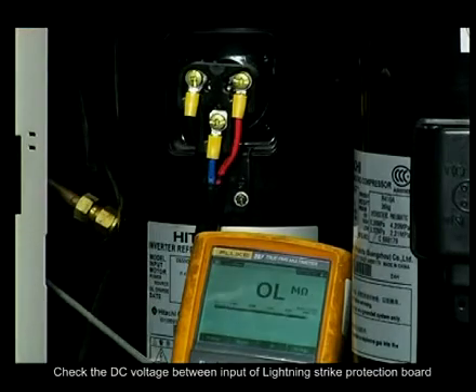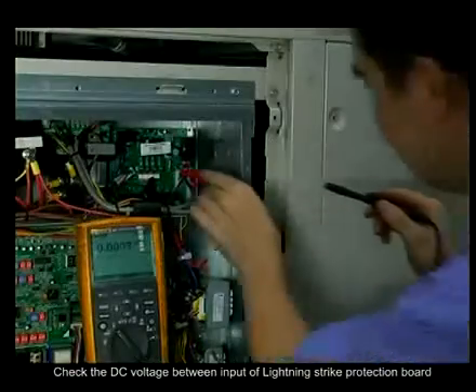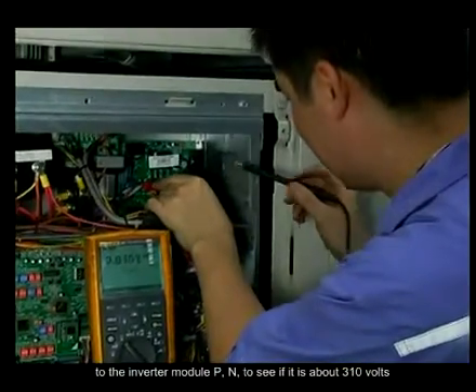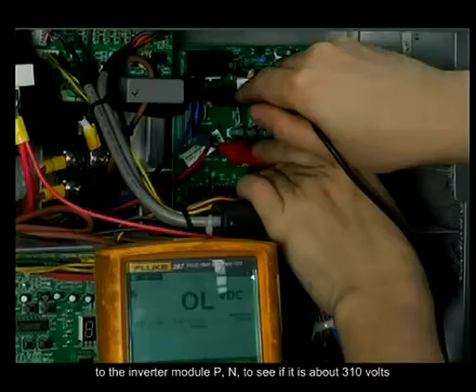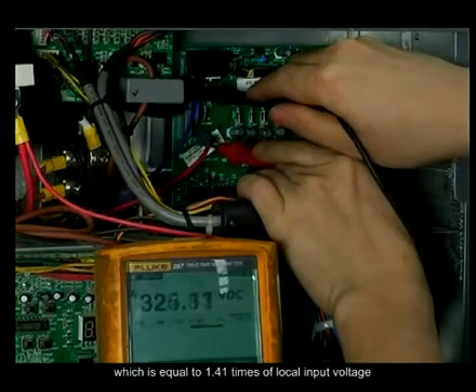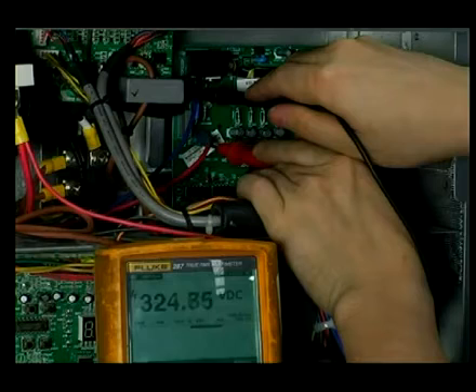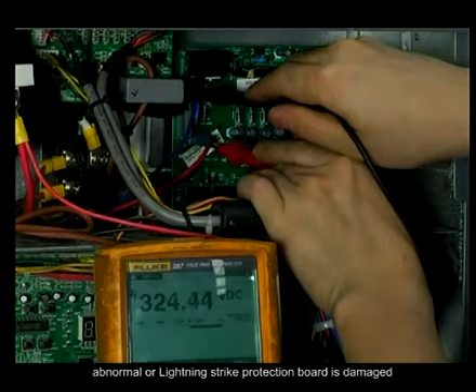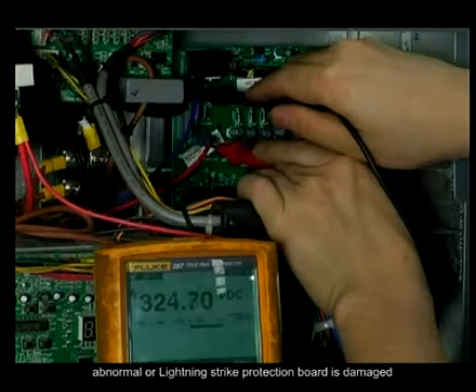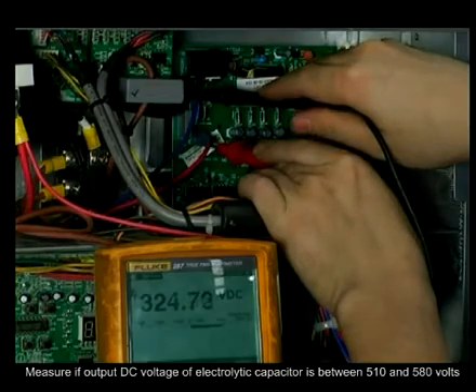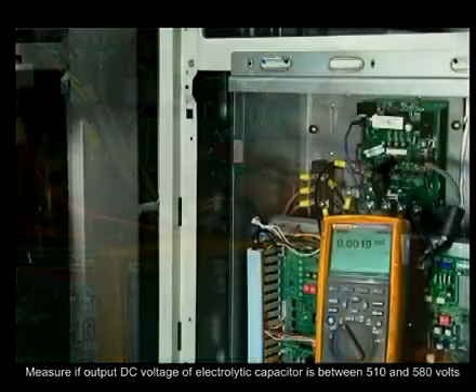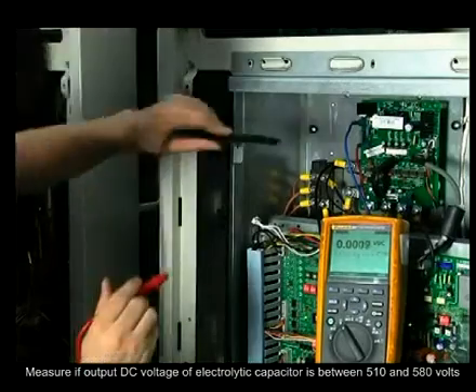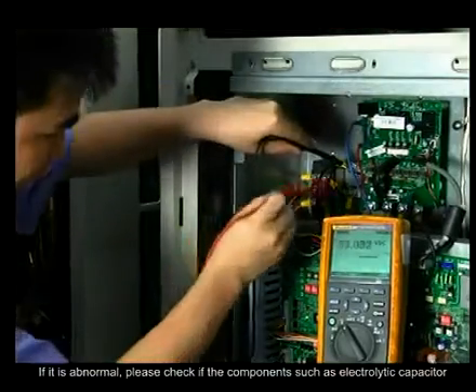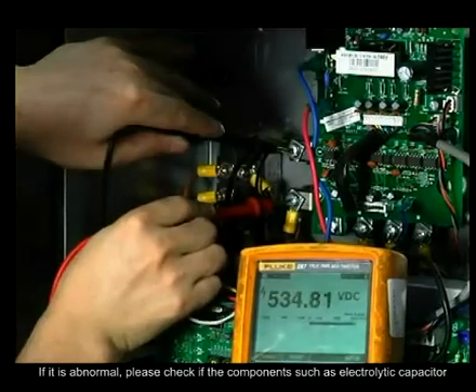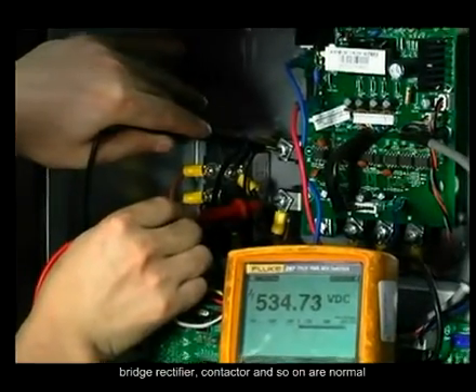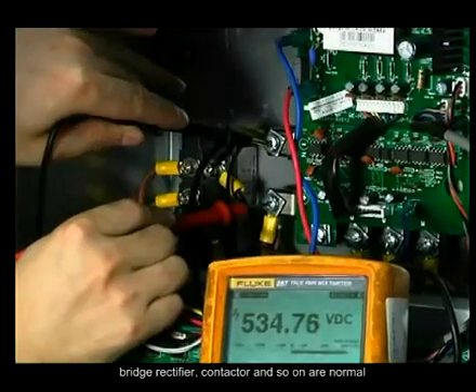Check the DC voltage between the input of the lightning strike protection board and the inverter module PN to see if it is about 310 volts, which is equal to 1.41 times the local input voltage. If it is abnormal, the voltage of the power supply is abnormal or the lightning strike protection board is damaged. Measure if the output DC voltage of the electrolytic capacitor is between 510 and 580 volts.